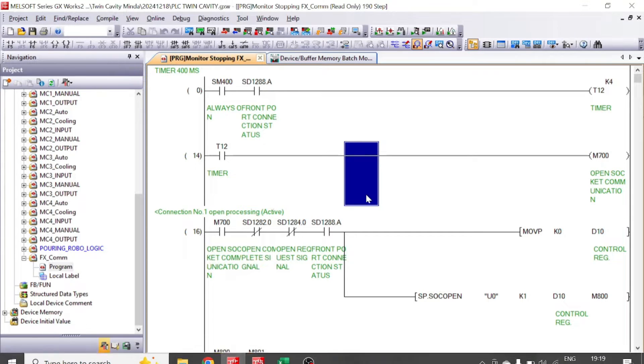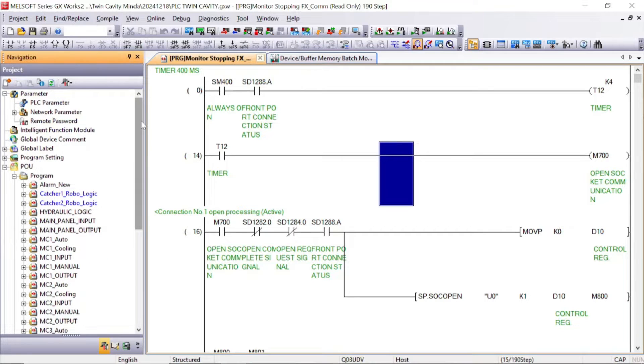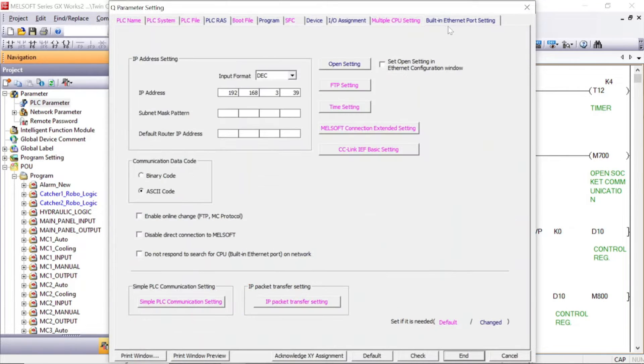First, we will write the program for Q series PLC. In Q series PLC, this is the program for the communication. First of all, we need to do some parameter setting in Q series PLC, so go to PLC parameter. In the built-in Ethernet port setting, this is our Q series PLC Ethernet IP address: 192.168.3.39.